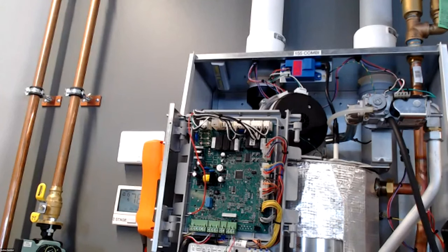When we use glycol, it's a little bit thicker than water. Water is moving slower, and it doesn't remove the heat as well through the heat exchanger. So we've reduced efficiencies and we have higher stack temperatures, and that's why we need to change from PVC on the venting with glycol. I hate glycol, we don't have to use it, you know, I'd rather not. But with glycol, definitely should be testing it once a year. And also you're probably gonna change it out with most manufacturers every 5 years. So just keep that in mind.